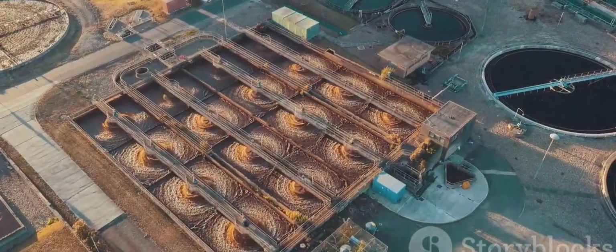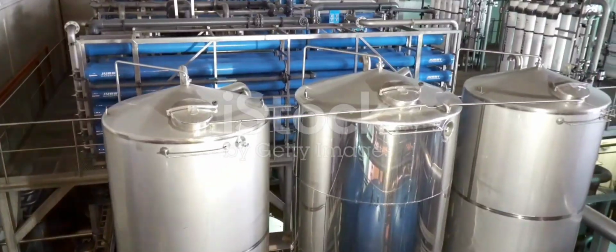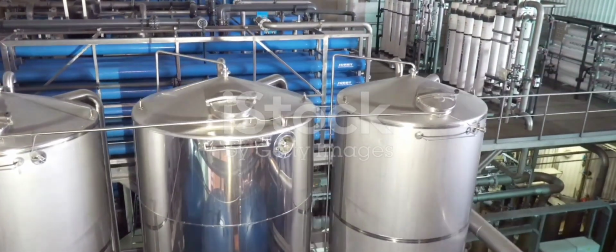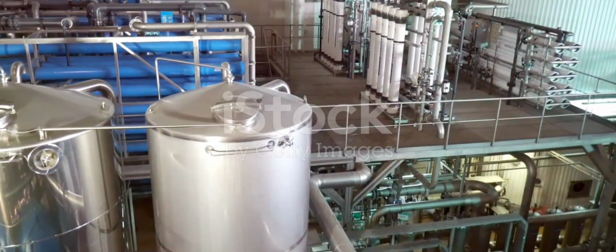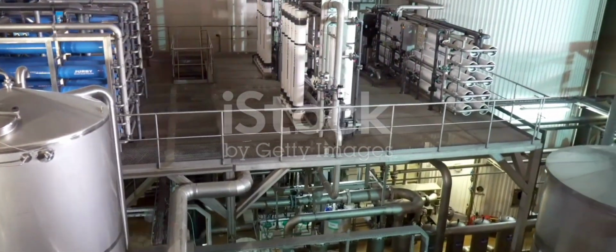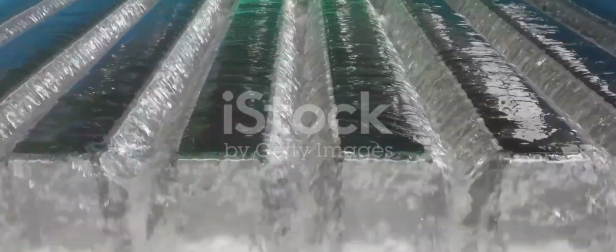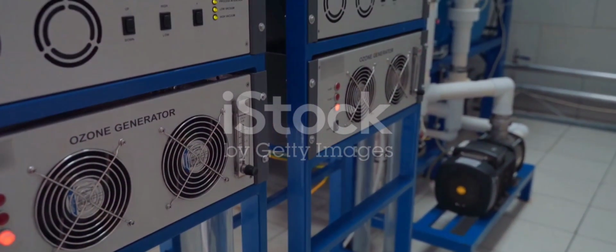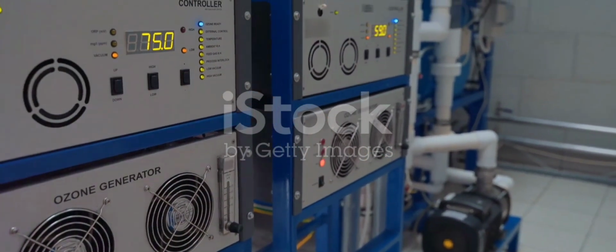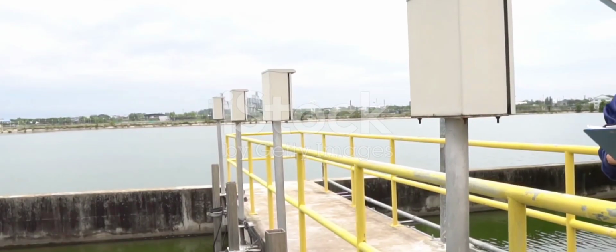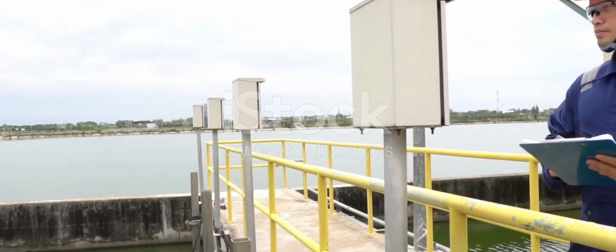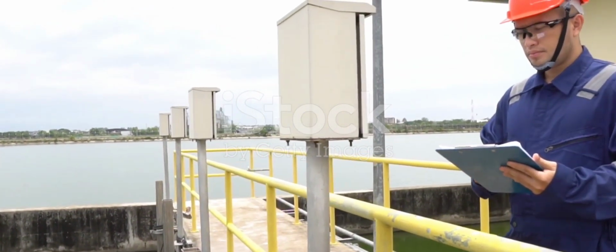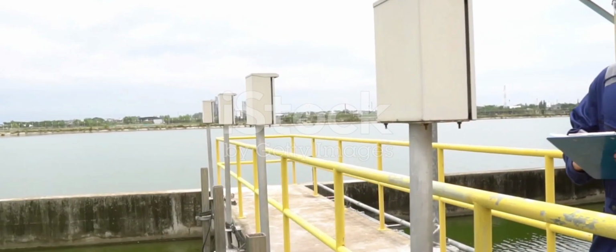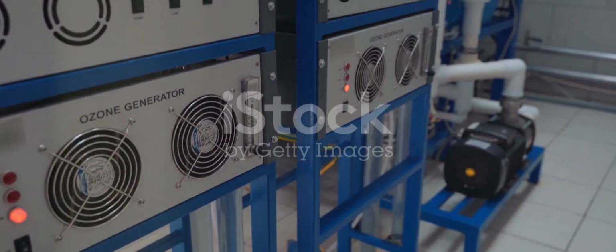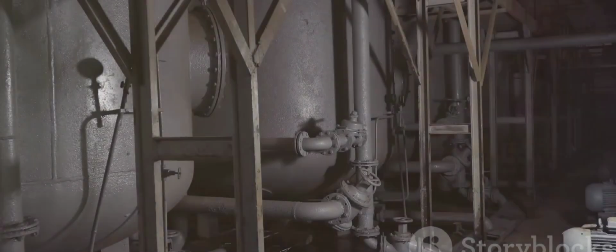Disinfection, which can involve chlorination, UV, or ozone. After filtration, the water is disinfected to kill any remaining pathogens and microorganisms. This is typically done by adding chlorine or through alternative methods like ultraviolet light or ozone. Key parameters to monitor are chlorine dosage, measured in milligrams per liter, contact time, also known as the CT value, residual chlorine concentration, UV intensity if UV disinfection is used, and ozone concentration if ozonation is utilized.